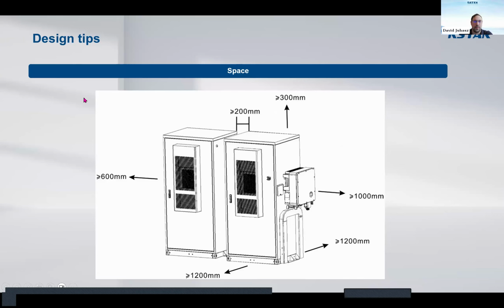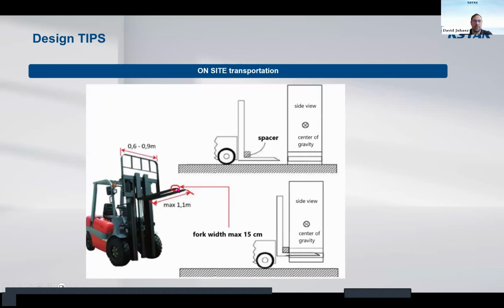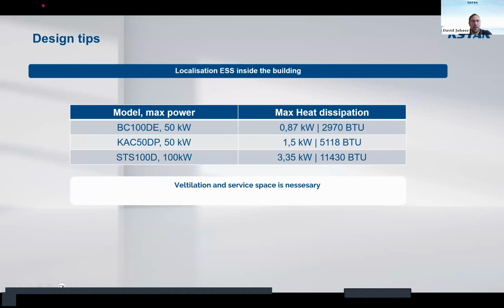There is necessary space for operation and maintenance. Regarding this, the fork width during the transportation always needs to be checked, because there is an extra metal part which can be dangerous if you don't pay attention to where you put the fork in. Okay, for the heat calculations inside the building, we have a lot of calculations for the heat dissipation, which you can consider.